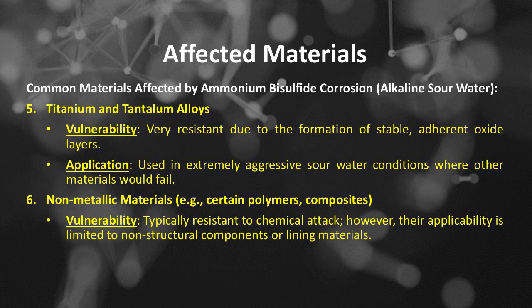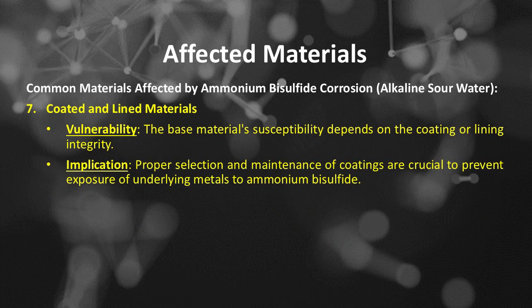Common materials affected by ammonium bisulfide corrosion or alkaline sour water, number 6, nonmetallic materials, such as certain polymers and composites. Their vulnerability: typically resistant to chemical attack, however, their applicability is limited to non-structural components or lining materials. Common materials affected by ammonium bisulfide corrosion or alkaline sour water, number 7, coated and lined materials. The vulnerability of coated and lined materials: the base material's susceptibility depends on the coating or lining integrity. The implication: proper selection and maintenance of coatings are crucial to prevent exposure of underlying metals to ammonium bisulfide.